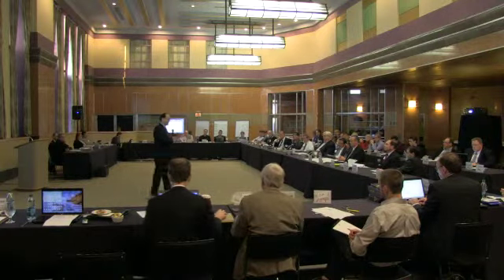It doesn't sound like much, and probably most of the energy savings isn't because of temperature, it's really driven by humidity. But by changing those set points, it really does affect the size of the equipment we have to put in place and the operating cost of the facility. So until we know where we're going with all that, it's hard for me to give a hard answer, but I'd expect the systems would be slightly larger than we have now.